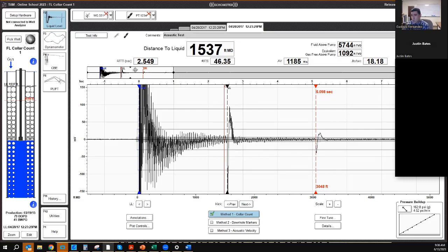Now we know the time to the liquid level is 2.5 seconds. So if I'm a service provider out in the field and I call you back and say, hey, your liquid level is 2.5 seconds from surface, would that information be enough for you? Say no, I need to know the distance to the liquid level. So how do we convert in this plot 2.55 seconds into distance?